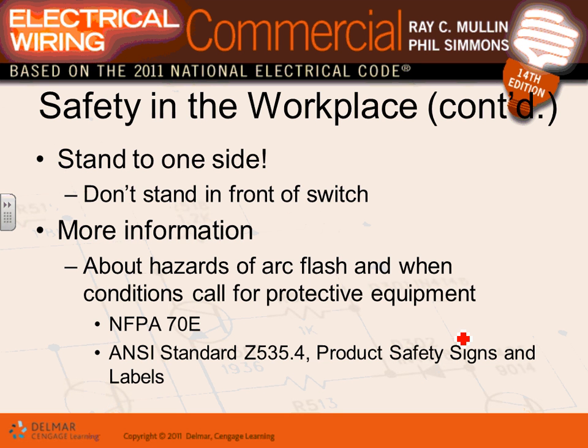Don't stick your head right next to them, and stand on one side, guys, don't stand in front of the switch gear. There are examples where people stand in front of the switch gear and open or close it, and the whole switch gear or panel or disconnect blew up right into their tummy and killed them. So they want you to stand to one side when you open and close this equipment. In this case, I'll be standing right here as I open and close this equipment.